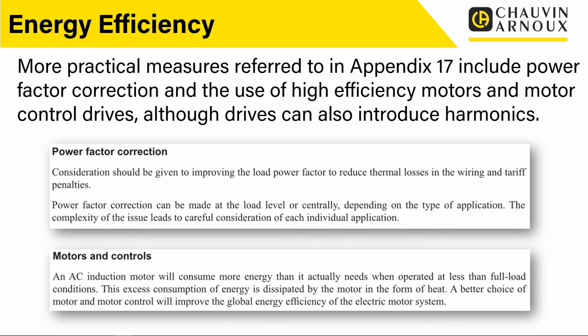So more practical measures referred to in Appendix 17 include power factor correction and the use of high efficiency motors and motor control drives. Although remember, if we are adding in motor control drives, they can introduce harmonics. So you do need to be careful that there's a knock-on effect there: when we're introducing something because it's more energy efficient, there will be a trade-off because there's harmonics in there and we have to allow for that. Power factor correction obviously is a very popular process, particularly in areas where we're using big inductive loads. However, it is important to make sure that they are designed and set up for the installation and for the loads that you are using.